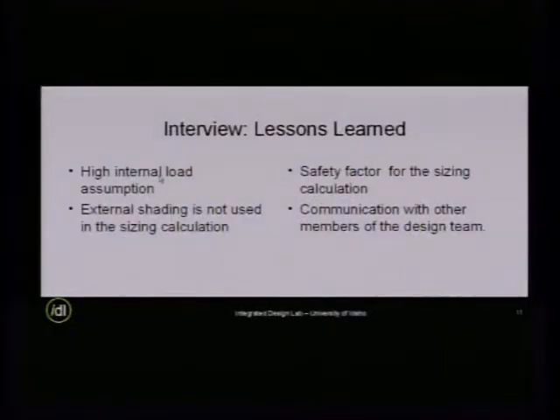The typical things that we found that can lead to oversizing. Number one is the high internal load assumption, especially for the old buildings. When we look at the lighting load, for example, some of the buildings were designed for 2 watts per square foot of lighting load, which is unheard of if you look at the code. The code level now is 1 watt per square foot. But for pre-code, this is pretty common. So, very high internal load assumption.